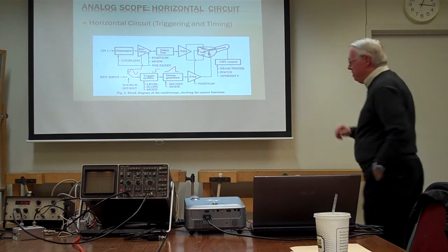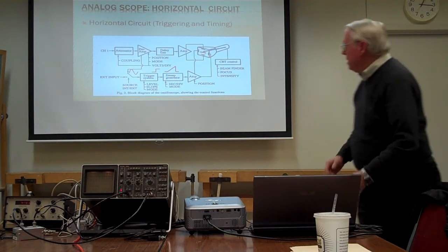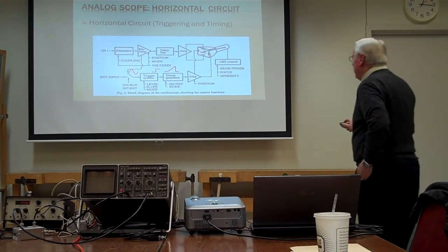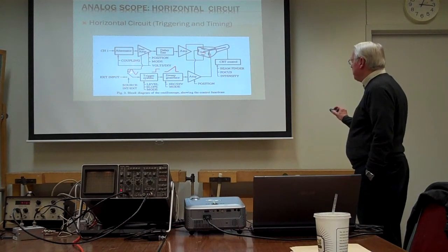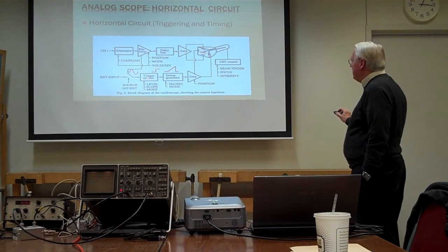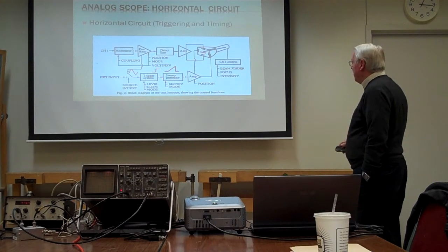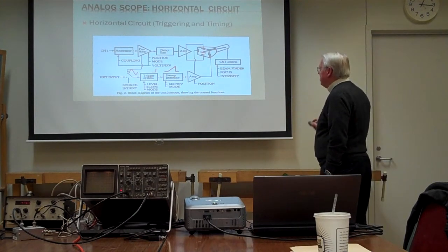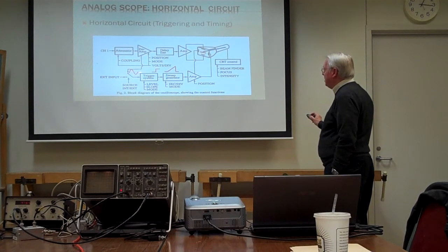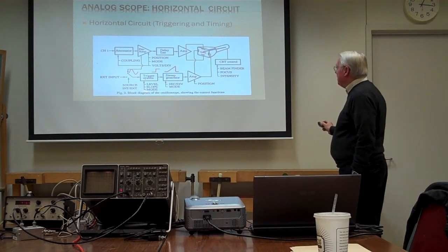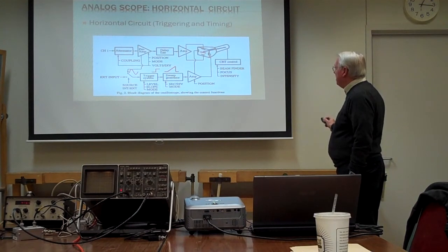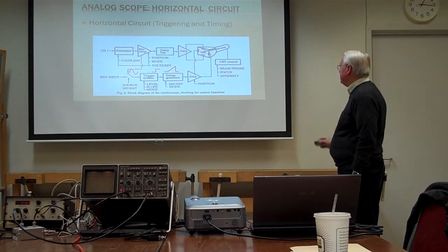Here's how the horizontal circuit works: we have the sine wave picked off from the vertical preamplifier and fed into the trigger system. It can generate either positive or negative going slopes to trigger on various points of the incoming signal, and then it generates a linear ramp. This ramp needs to be linear so we get a consistent time per division along the horizontal axis.